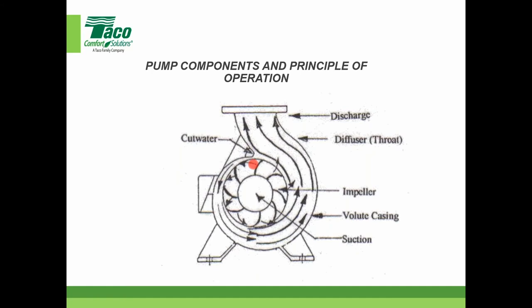And that dimension and that cut water design is another very important piece of the puzzle to make a pump very efficient. And notice this picture is actually showing very little space. You can see where my red, hopefully you can all see the red dot there. There's little space, very little space between the impeller and the cutwater. So I'm pretty sure this picture represents a maximum impeller. Us pump manufacturers can trim that impeller all the way down almost to the hub of the impeller. There's an actual meaty piece there. I call it the hub. So it's not unusual for us to trim an impeller. We could trim it probably upwards of 3 to 4 inches.